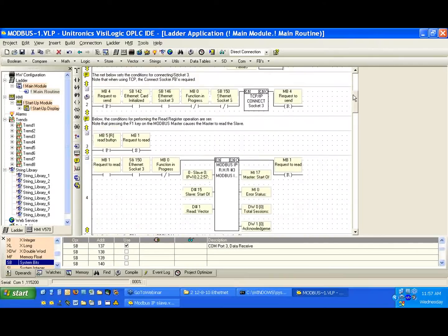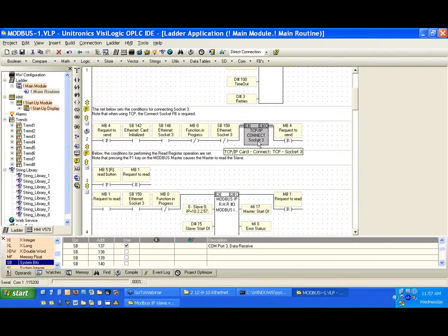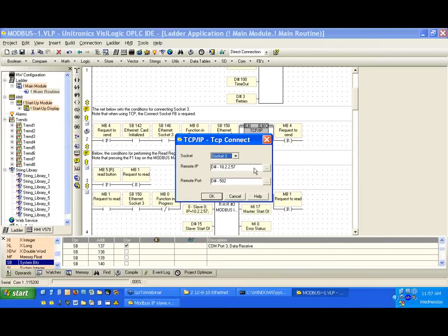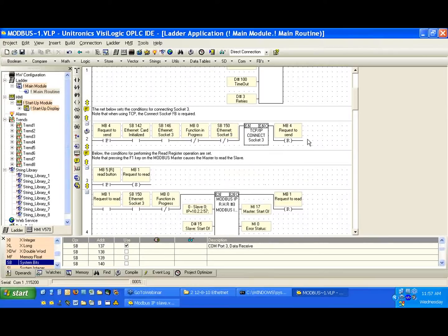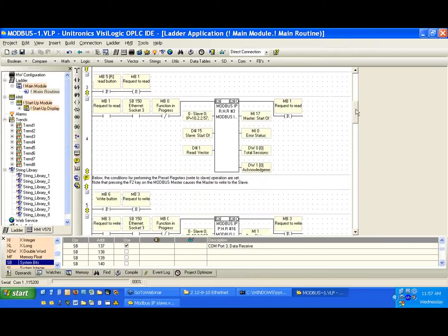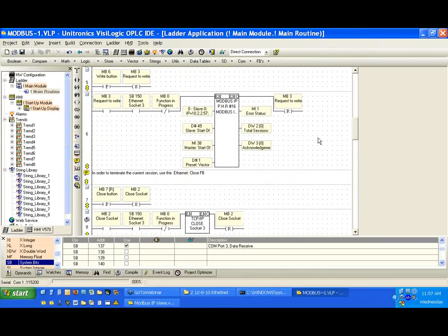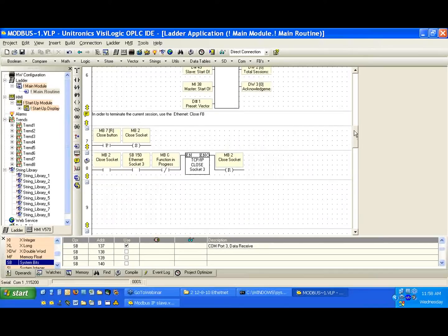The second controller using either a second TCP/IP connect or, in this case, an indirect address. Or we can use socket 1 for one communication and socket 2 for another communication. If we had over 4, if we had 5 or 6 or 7, we wouldn't have the option to keep all communications dedicated per socket, so we'd need to figure out some configuration that we can close and open sockets with different IP addresses.